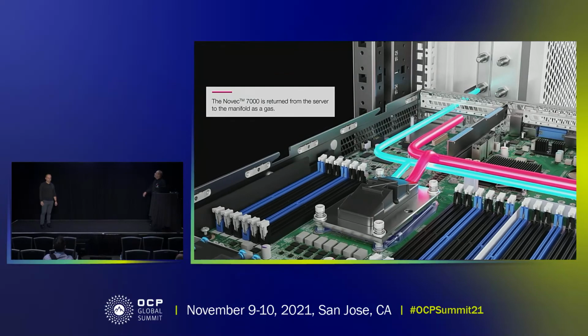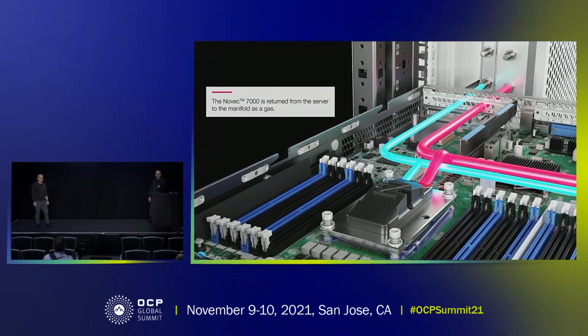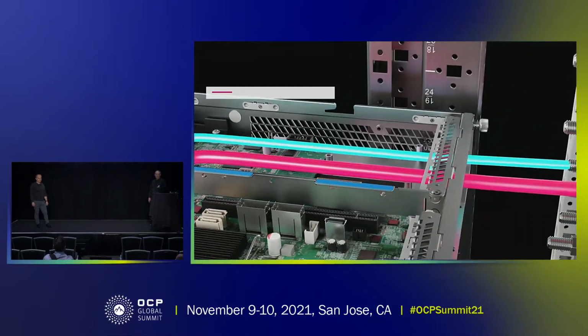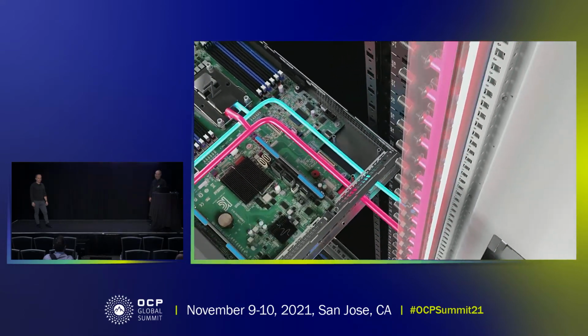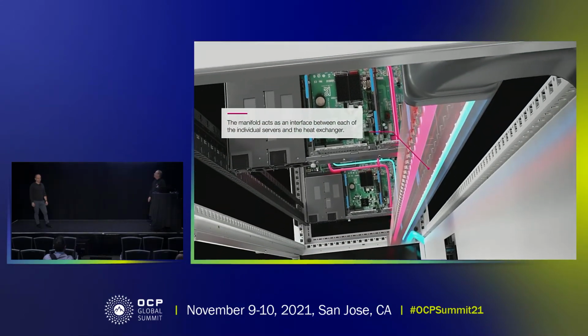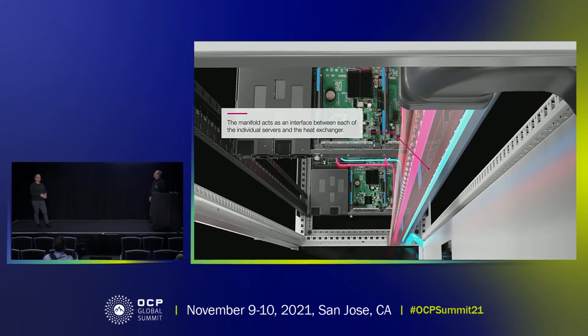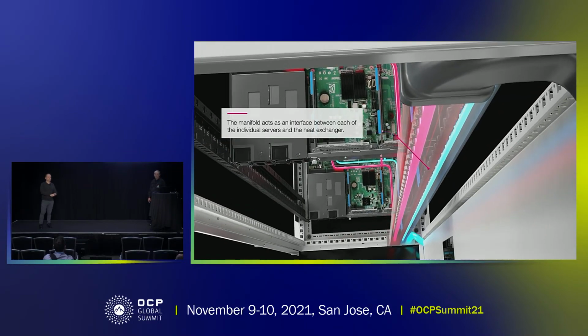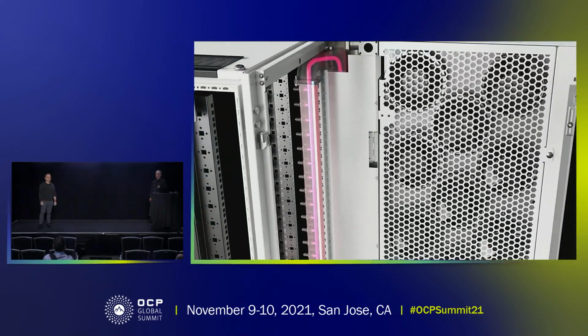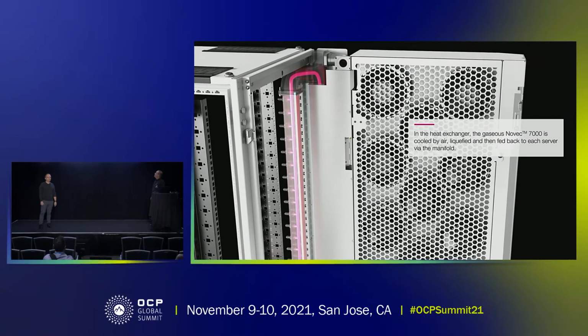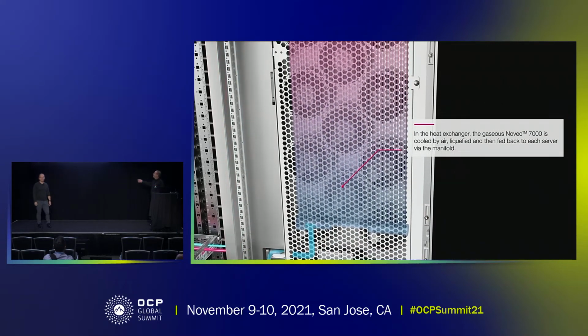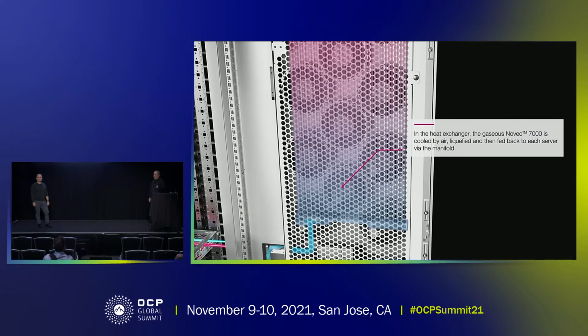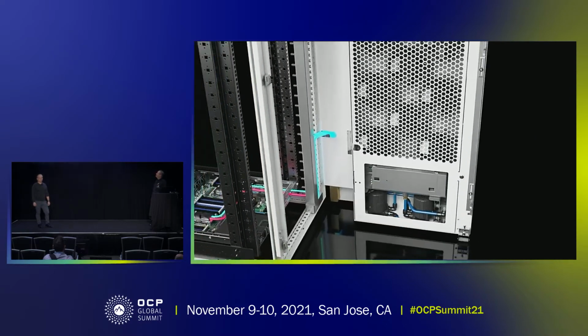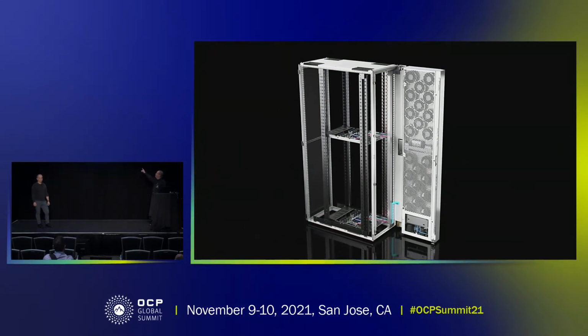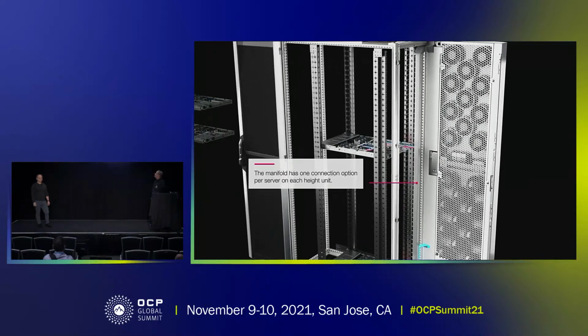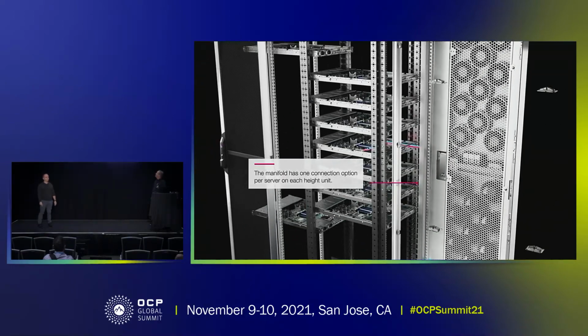The important thing to see is that the servers don't change. The tubing is nylon, very flexible, and doesn't endanger anything or require changes in the server. It connects to the manifold just like the PDU, without needing to change anything in the rack, and then connects to the heat rejection unit, shown here as an air-based rear door with a buffer on the bottom and pumps that send the liquid back into the servers.